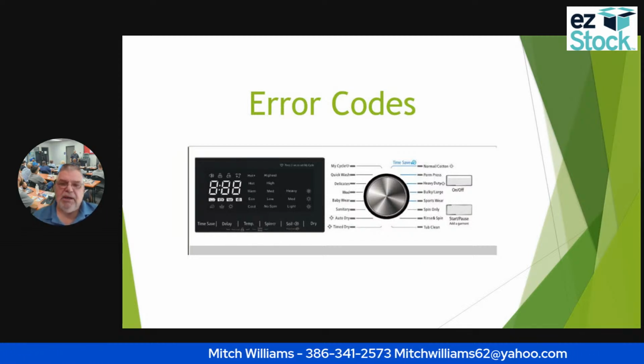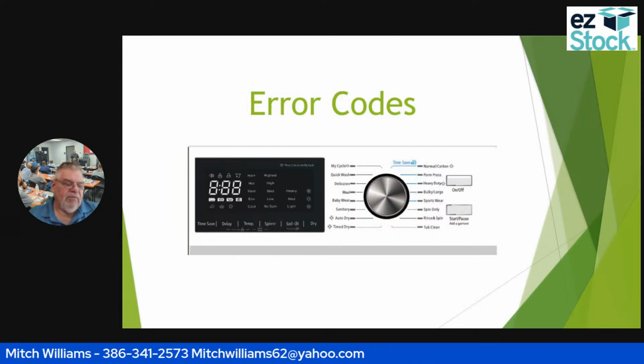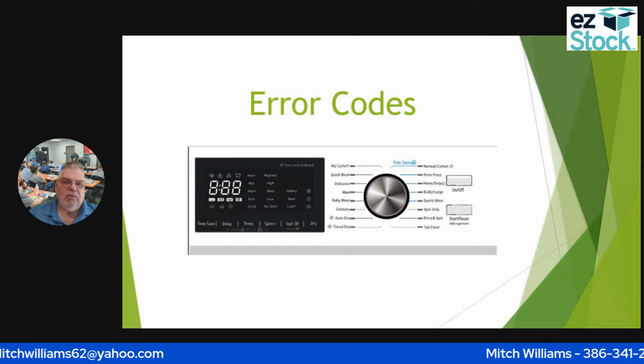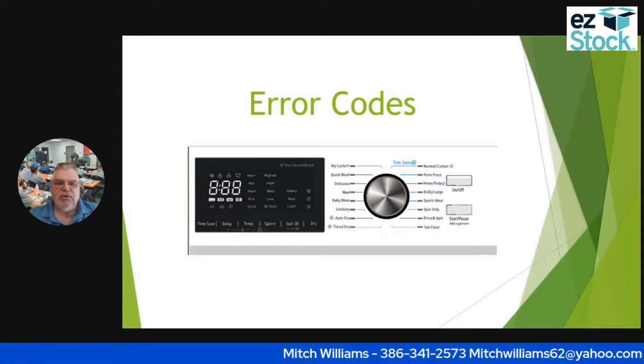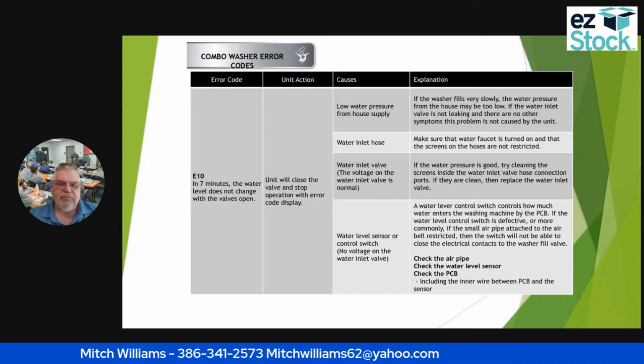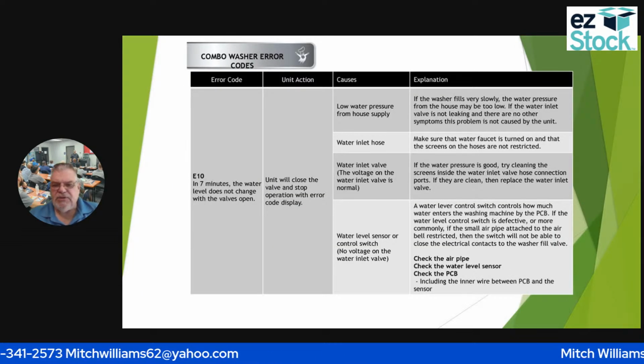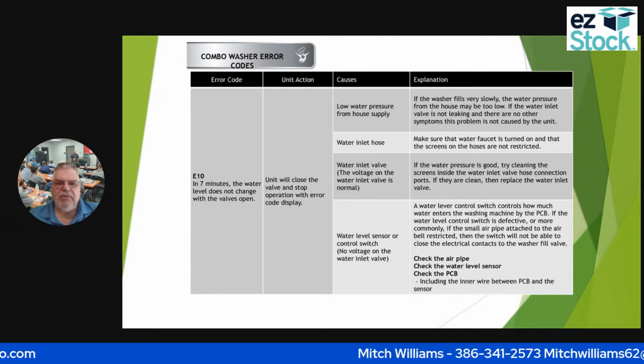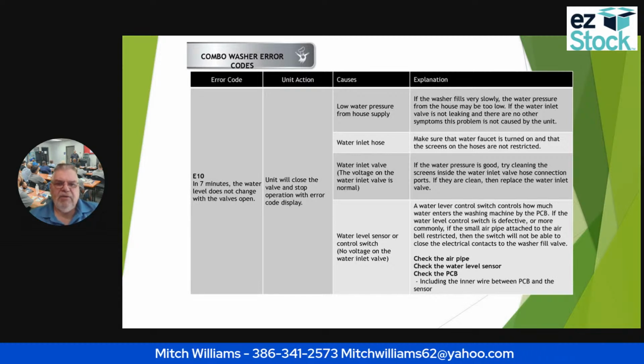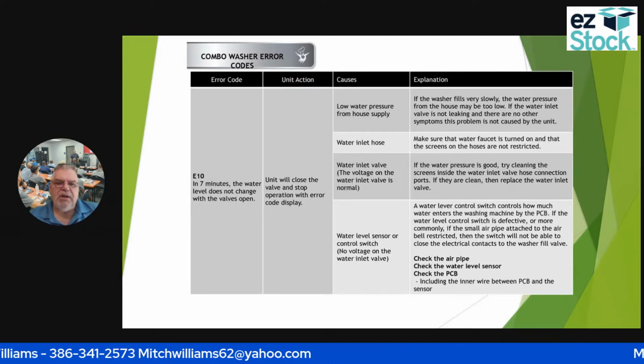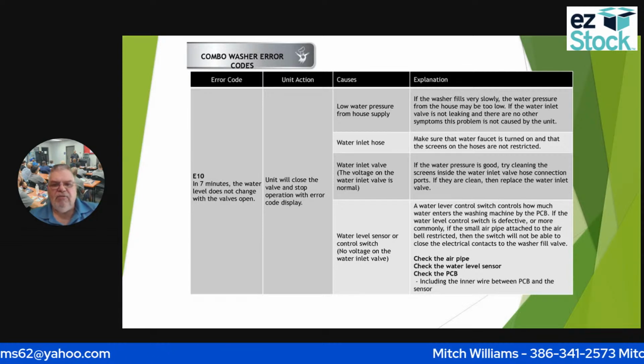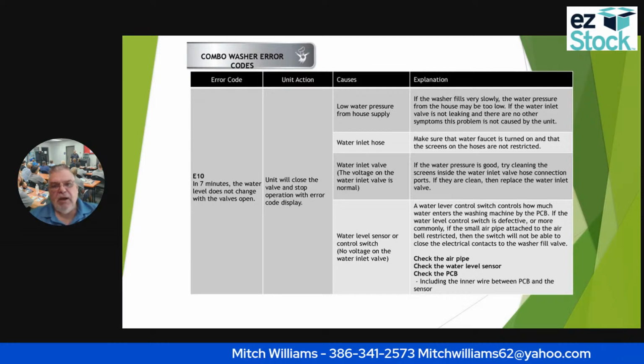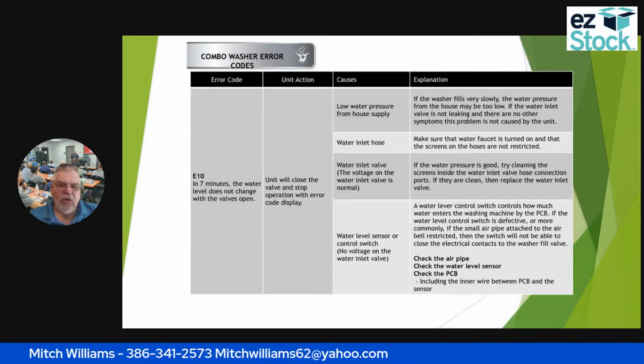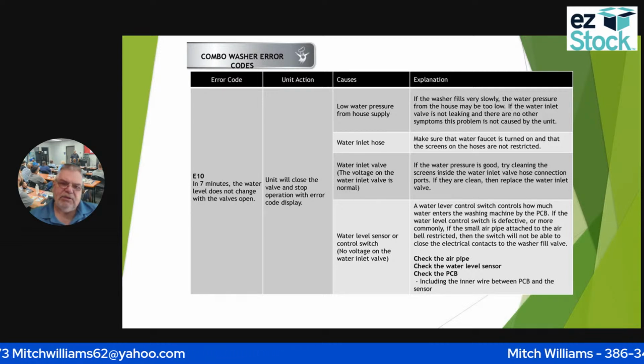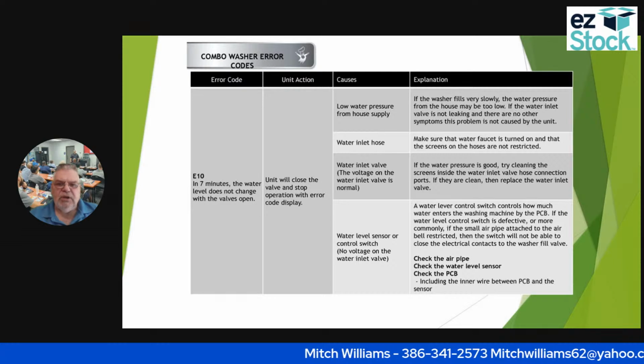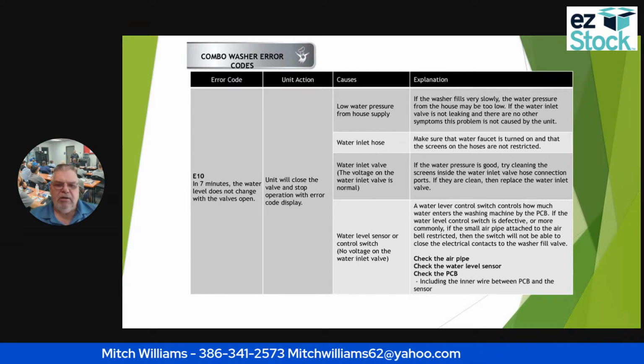The first thing that we want to talk about is the error codes. That's if I'm going to do work on this unit, I want to be able to know what the error codes are. So how do I tell what the error codes are? If this error code populates in my little display, if I get an E10, it's telling me that in 7 minutes the water level did not change with the valve open. So that tells me that I have a water issue. If I open the door to it and I've got plenty of water in it, then that tells me that I have a board issue. Just simple stuff. So the unit will close the valve and stop operation with an error code in the display.